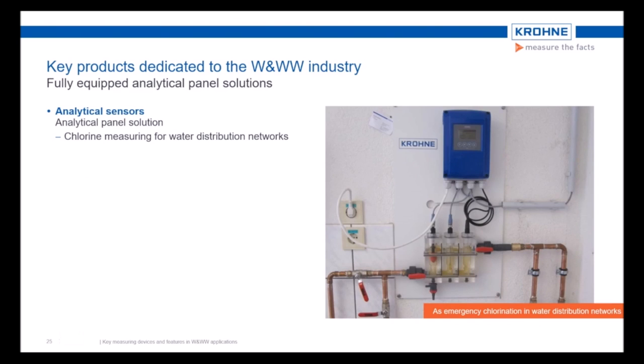To ensure the appropriate water quality from the outlet of a waterworks or a water treatment plant, even up to the end user's water tap, we need to disinfect the water here and there. This is realized with chlorine, which is mainly used due to the long sustainable depot effect and, of course, due to its cost efficiency compared to alternative disinfection methods. However, every country gives limit values for free chlorine remaining in potable water, which is mostly regulated by the local water authorities and regulations.